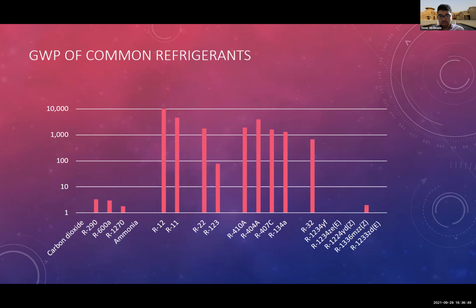On this chart, we simply summarize the difference between the global warming potential for different refrigerants. On the left-hand side, these are the natural refrigerants. You can see carbon dioxide as 1. This is a log scale, so you can see that this is 1, this is 10, 100, 1,000, and 10,000. The natural refrigerants are all below 10. The first generation of fluorinated refrigerants like R12 and R11 were quite high, more than 10,000 for R12. I capped it here at 10,000, but it is actually more than that. For R11, it's quite high, close to 7,000 or so.